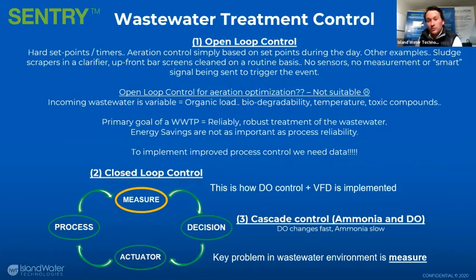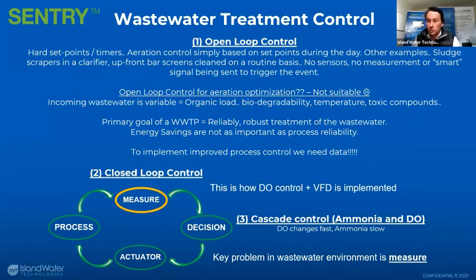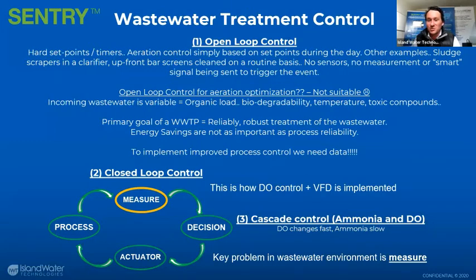Moving to closed loop control: we have a process, sensors providing information from the wastewater stream that allows us to make decisions, which can implement an actuator to turn a blower on or off, turn on a pump, or close a valve. All the way to more refined cascade control, using multiple sensors providing levels of insight. But the same problem always remains: wastewater is a challenging environment for sensors. If you're using light-based sensors in an environment where biomass loves to grow on all surfaces, it's very challenging to generate data you can reliably depend on consistently.